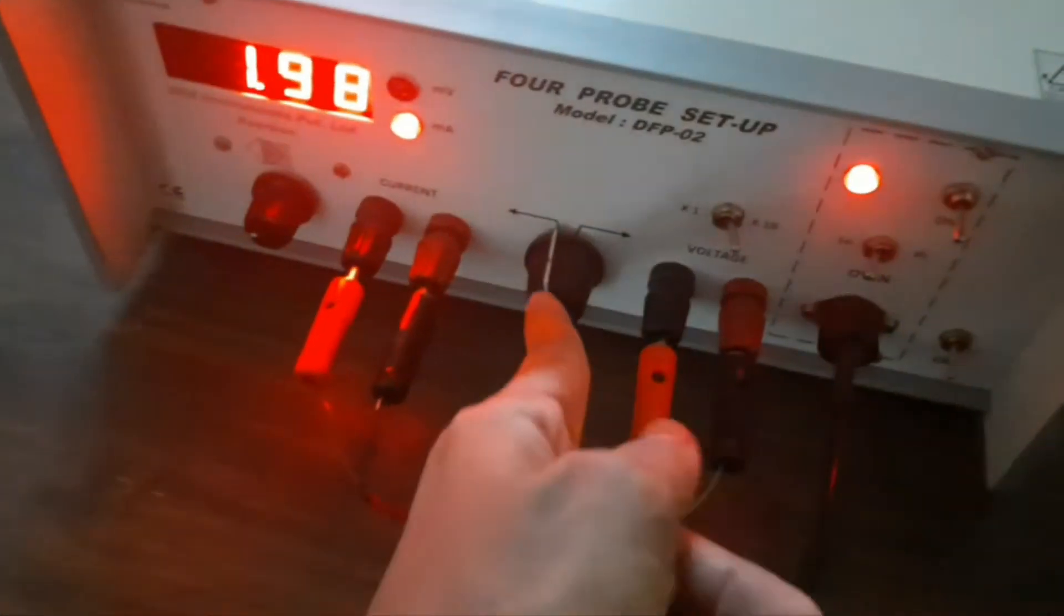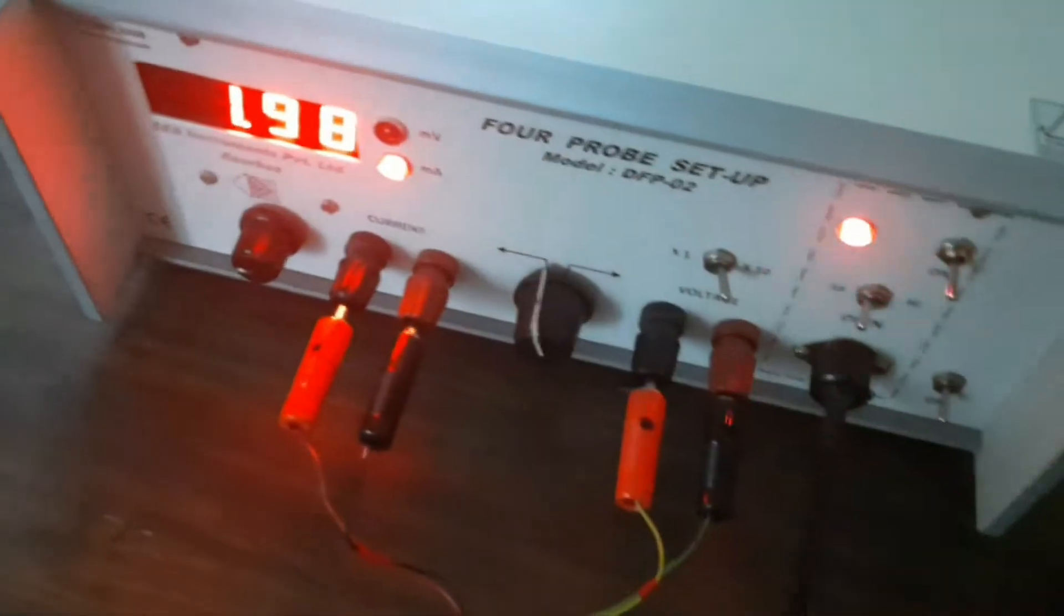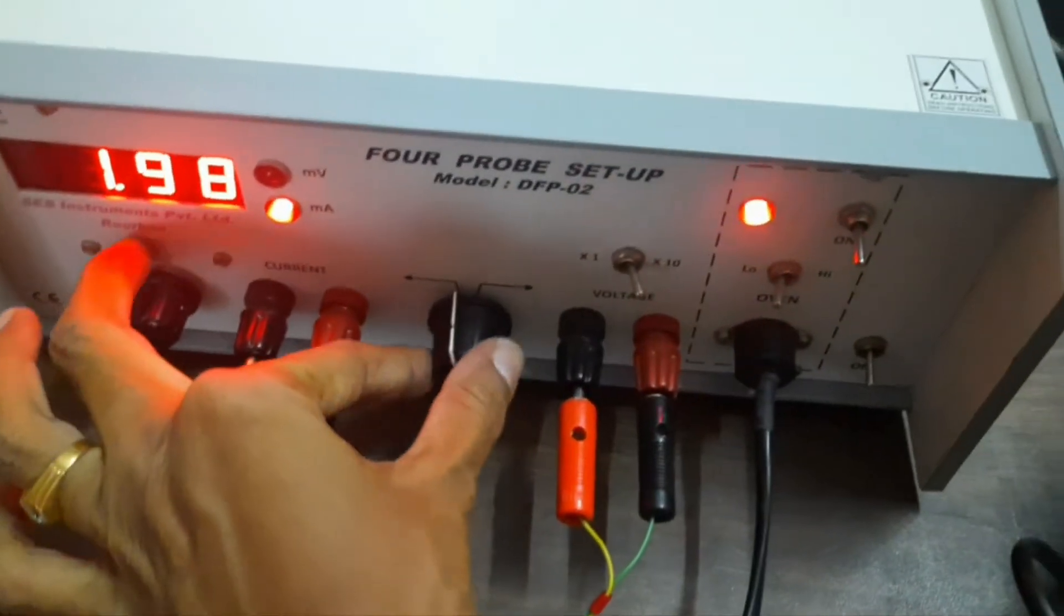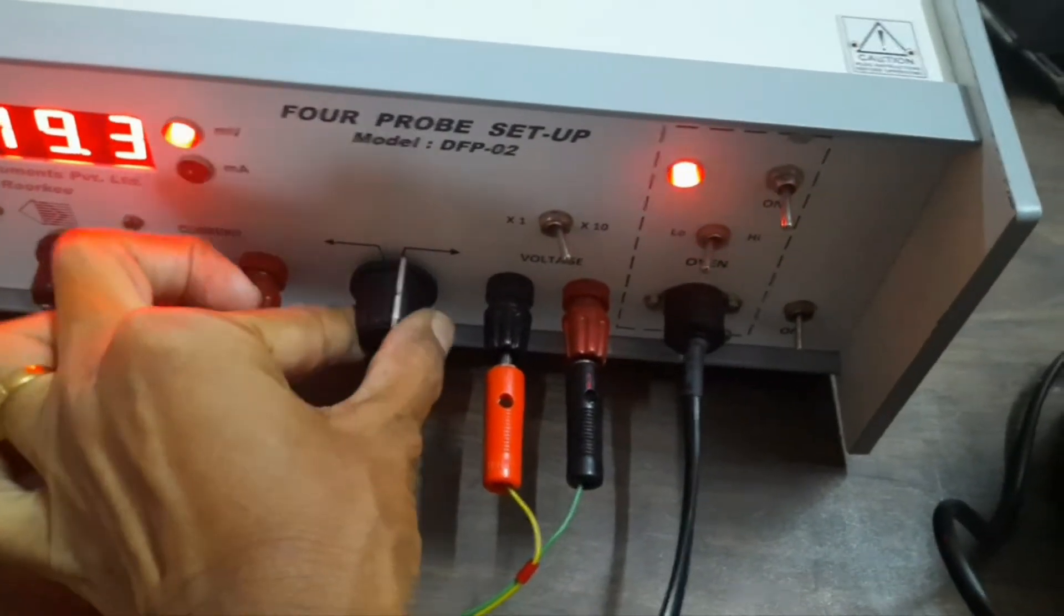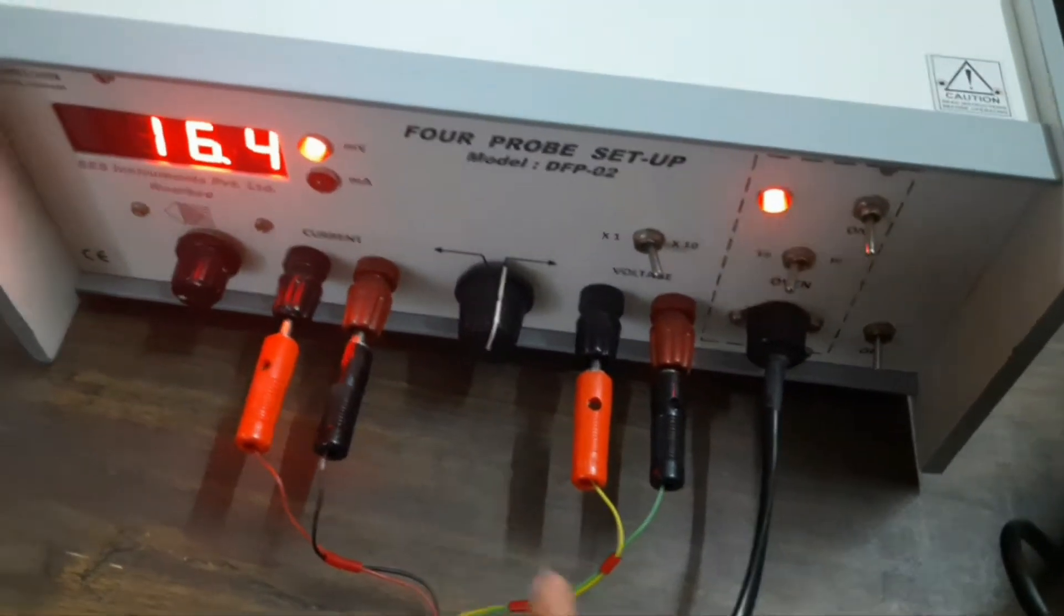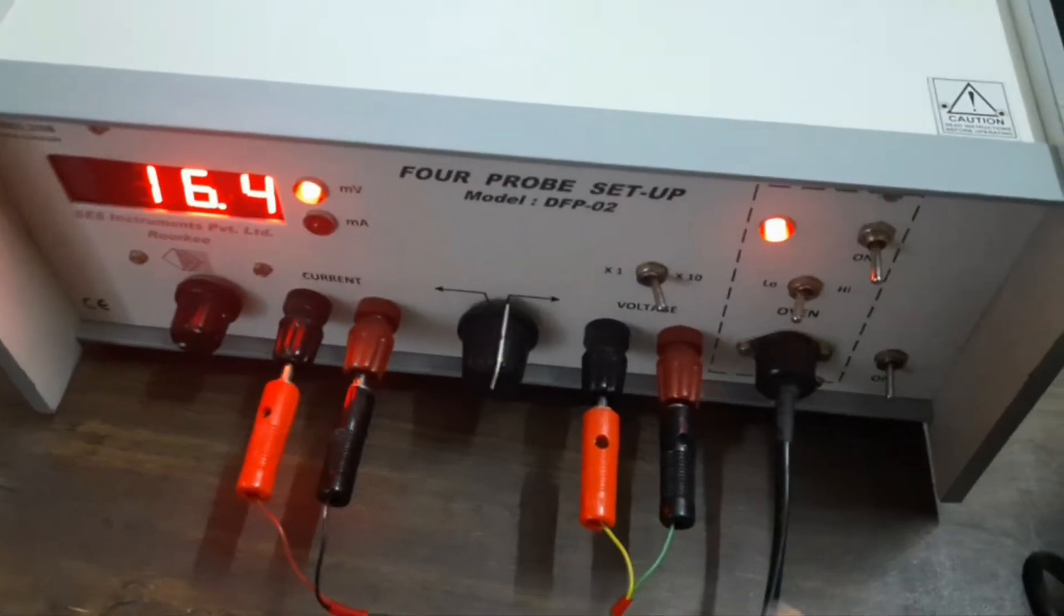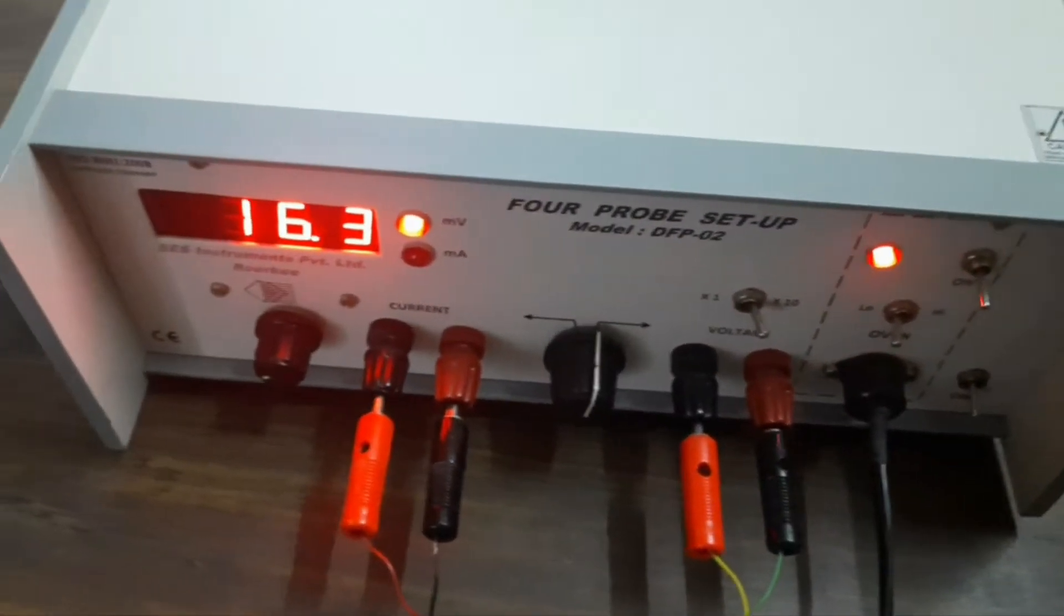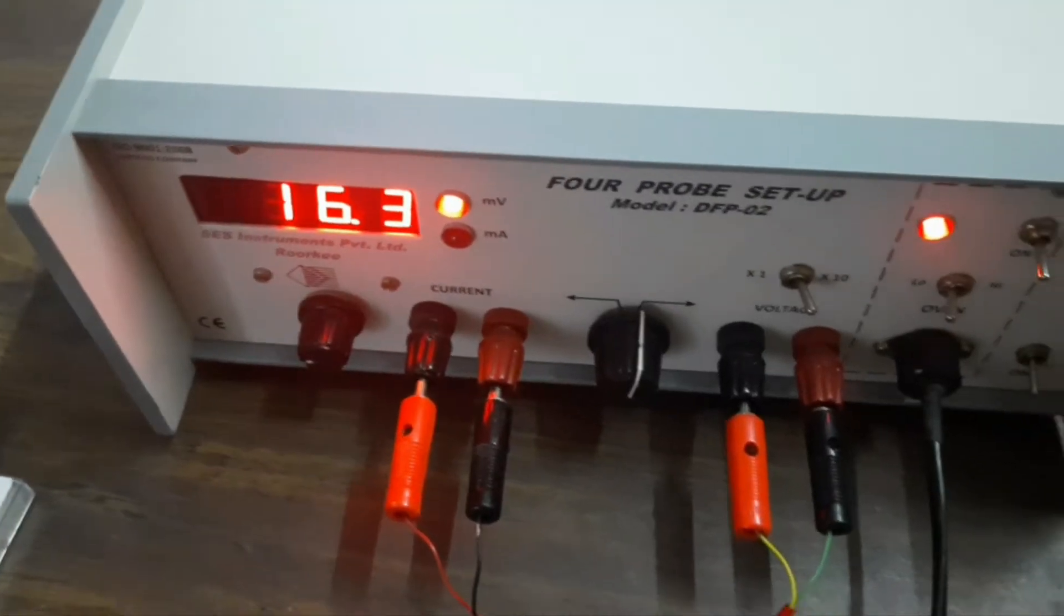If we want to note on the voltage, we should keep this knob at the voltage mode. Voltage mode we have to keep. So here we have to, this is in millivolt, 16.3 mV, like this.